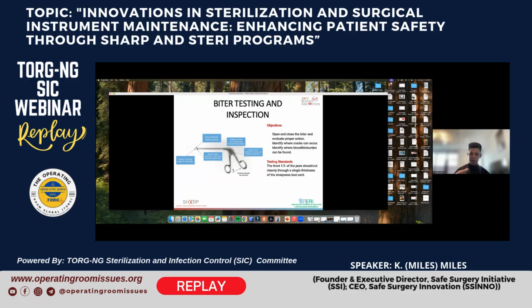So that's just a brief breakdown of our surgical instrument inspection guide. It goes into a lot more detail during the program, which teaches you how to actually test those instruments. So during this little brief discussion, we talked about how to inspect, so doing visual and tactile inspections of the instrument. But then there's also another side of that where you're actually able to test the instrument for functionality.